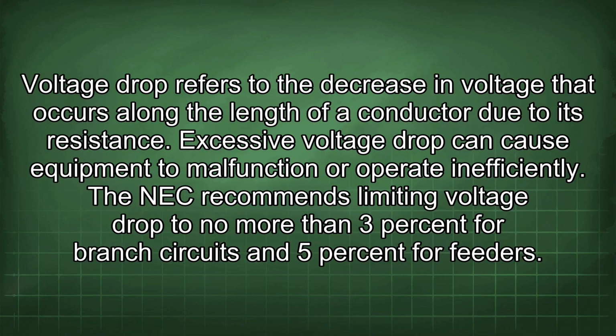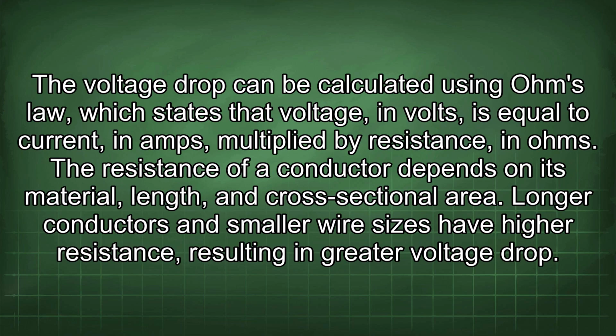Voltage drop refers to the decrease in voltage that occurs along the length of a conductor due to its resistance. Excessive voltage drop can cause equipment to malfunction or operate inefficiently. The NEC recommends limiting voltage drop to no more than 3% for branch circuits and 5% for feeders. The voltage drop can be calculated using Ohm's law, which states that voltage, in volts, is equal to current in amps multiplied by resistance in ohms.